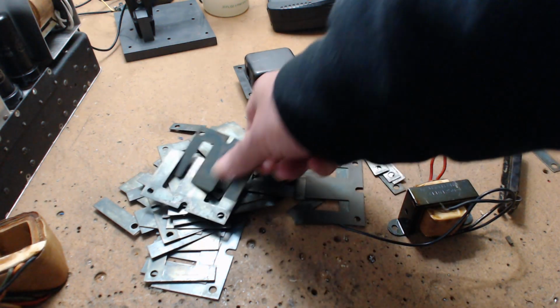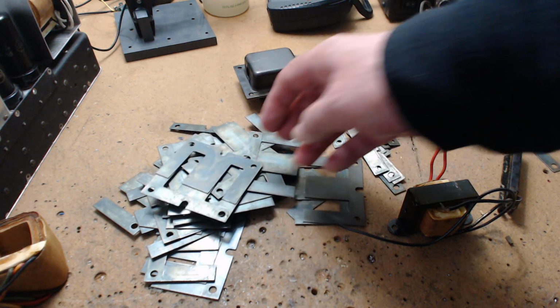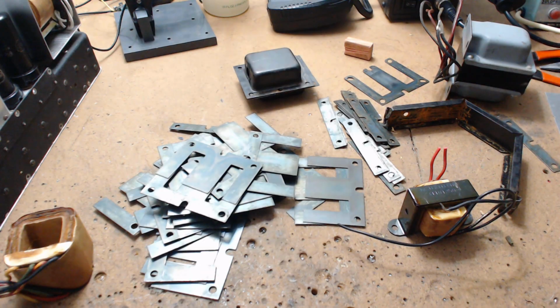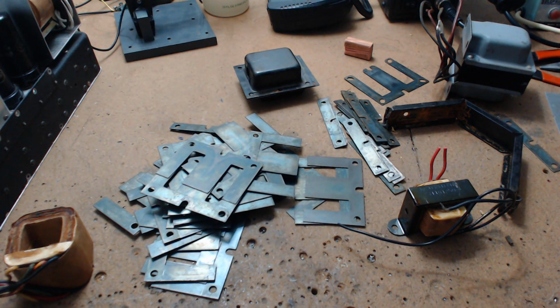What happens with an eddy current is basically a short against the transformer itself, and it causes the transformer, just sitting idle with the 110 across it, to warm up, and if the eddy current's real bad, it'll warm up even more. So the transformer is wasting power even though it doesn't have anything hooked on the secondary.